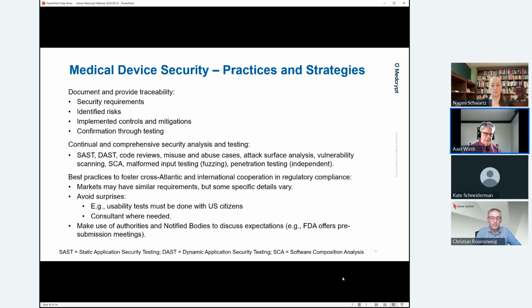One point that is emphasized repeatedly, and we have seen a lot of pushback if it was not followed, is the aspect of traceability, right? You establish your security requirements, you identify security risks, and you implement controls and mitigations during your development. But then in the end, you need to confirm that you meet your requirements and that your identified risks are mitigated through testing, right? So make sure that you have complete traceability from requirements over risks, over your controls, to testing, confirming that those controls address the risks and work as intended.